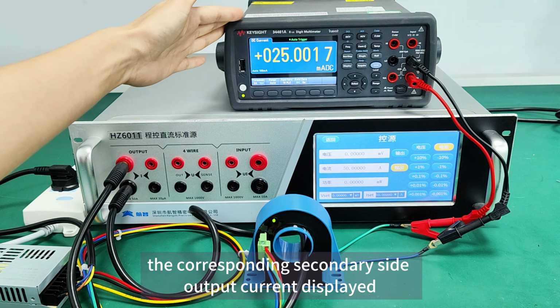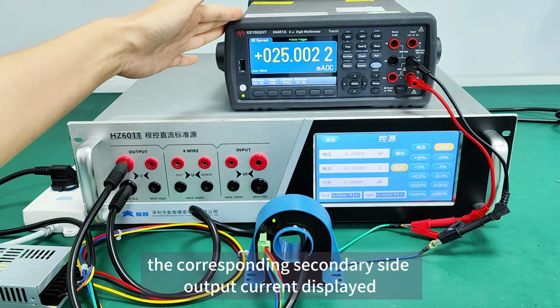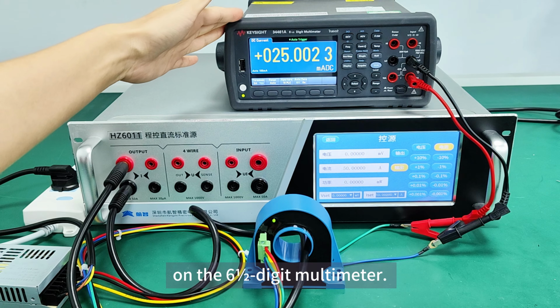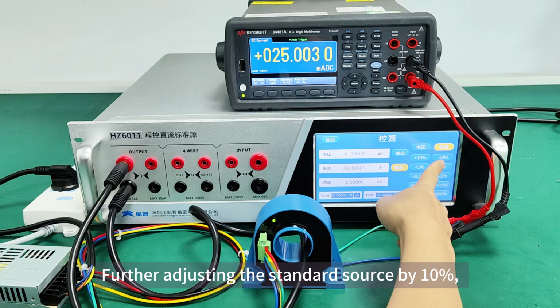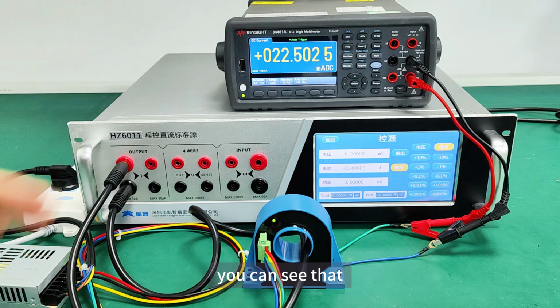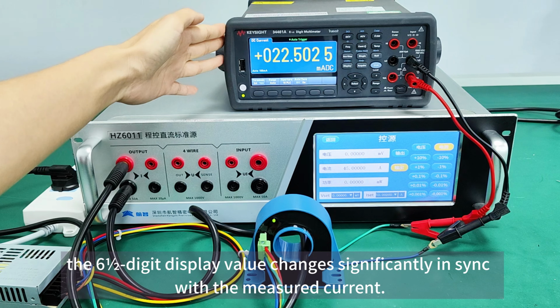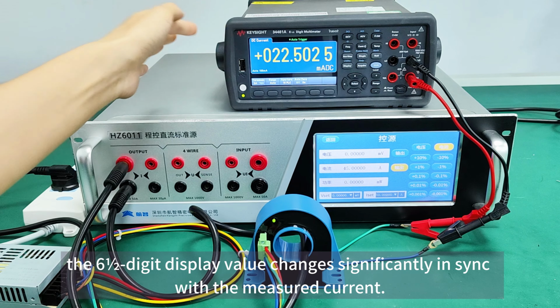And you can see the corresponding secondary side output current displayed on the 6-digit multimeter. Further adjusting the standard source by 10%, you can see that the 6½-digit display value changes significantly in sync with the measured current.